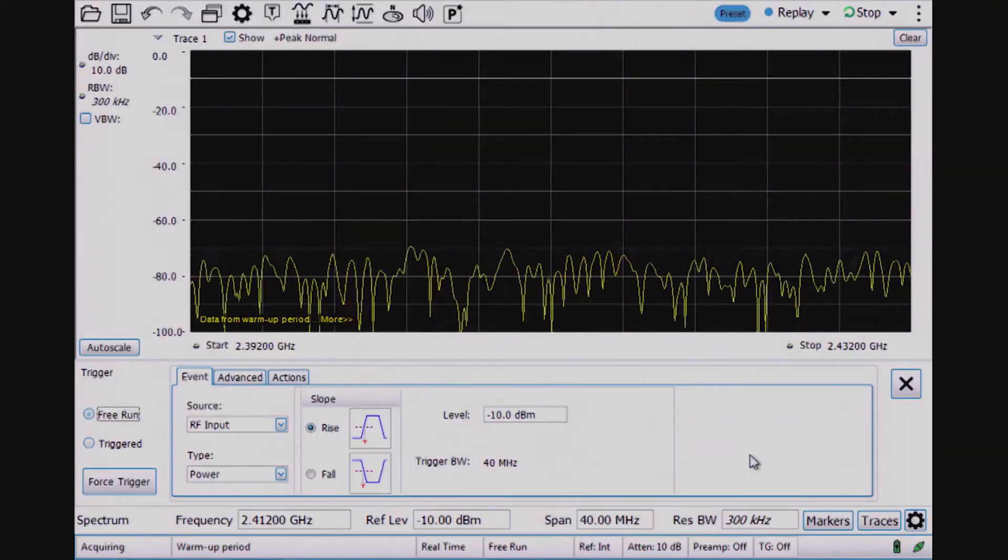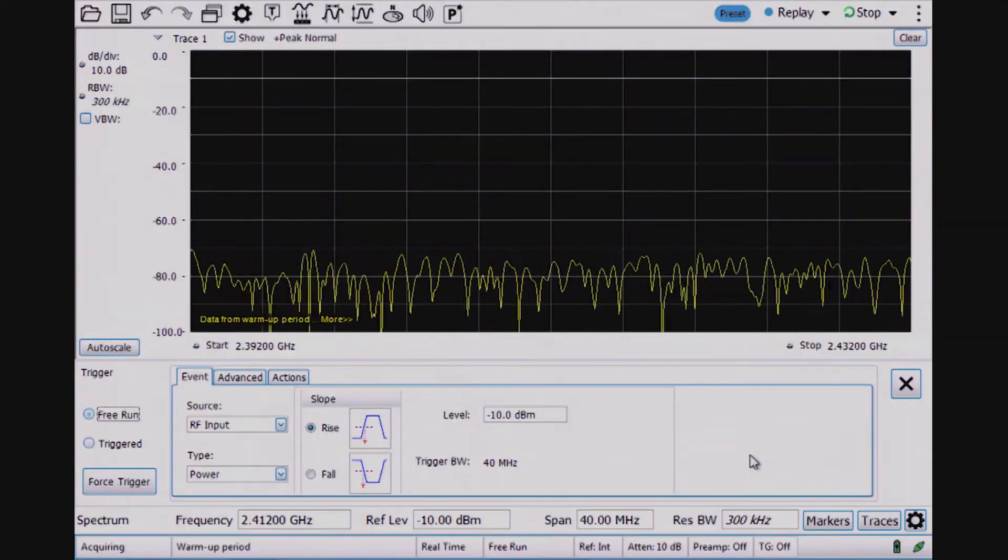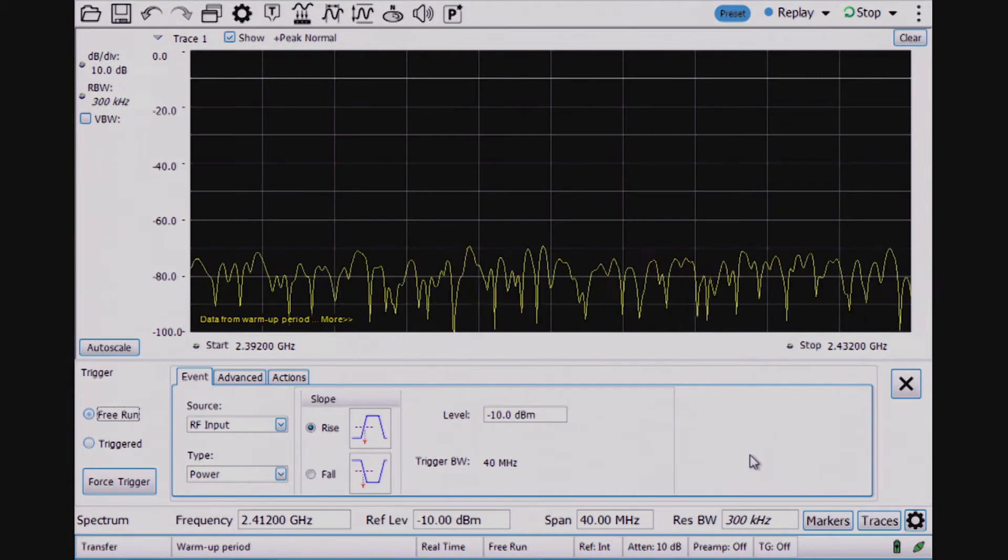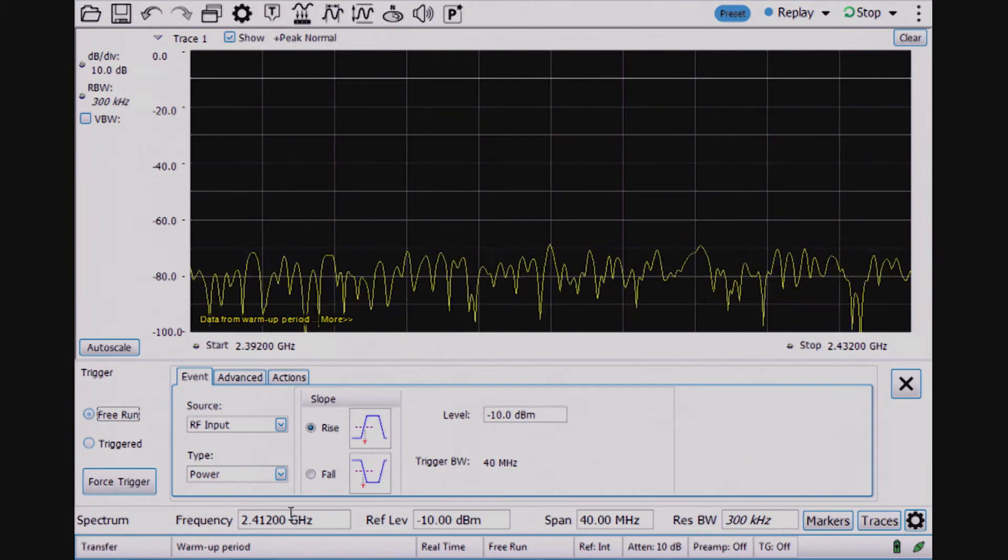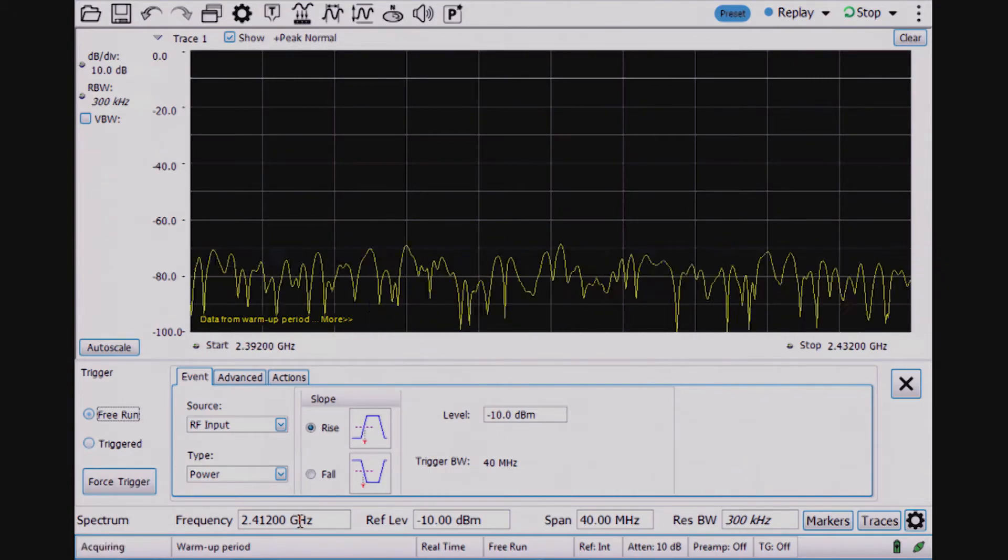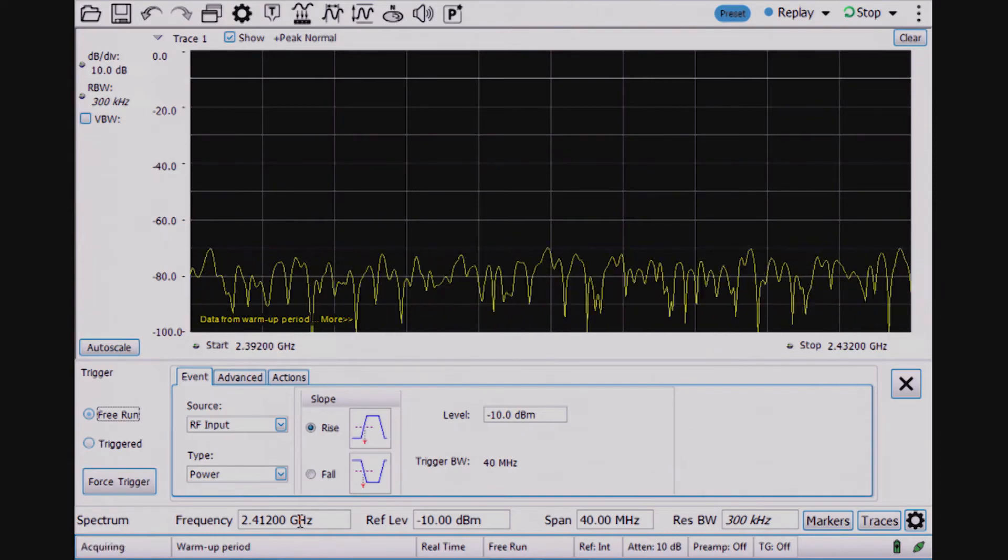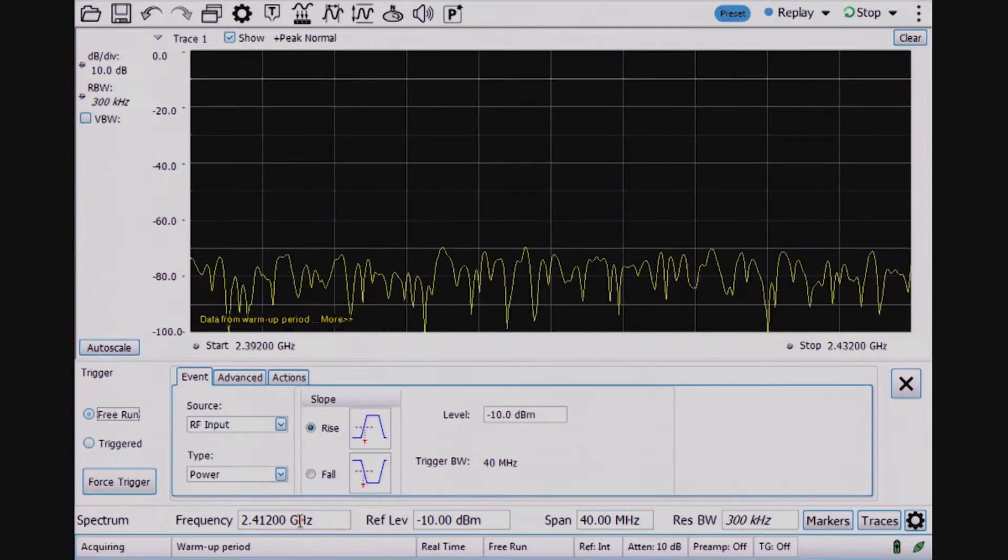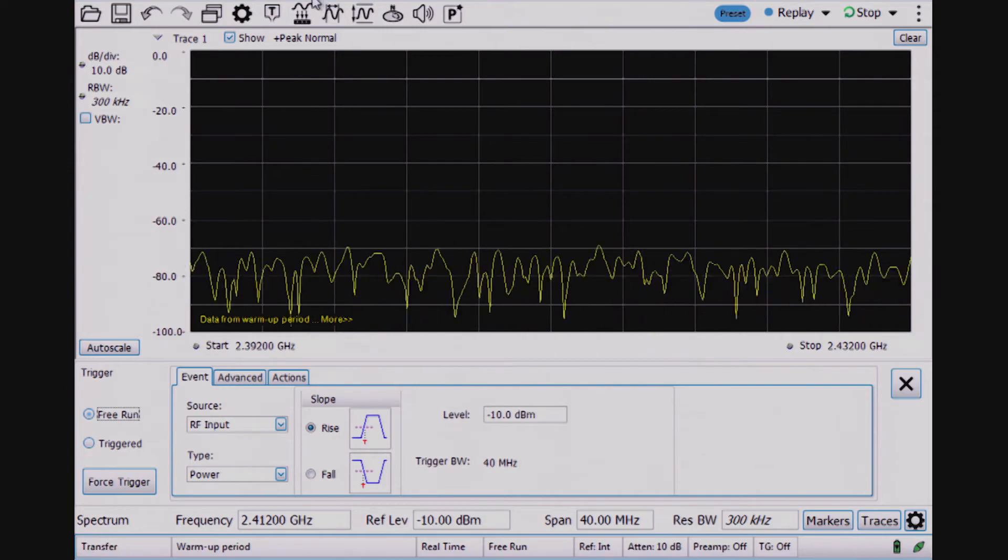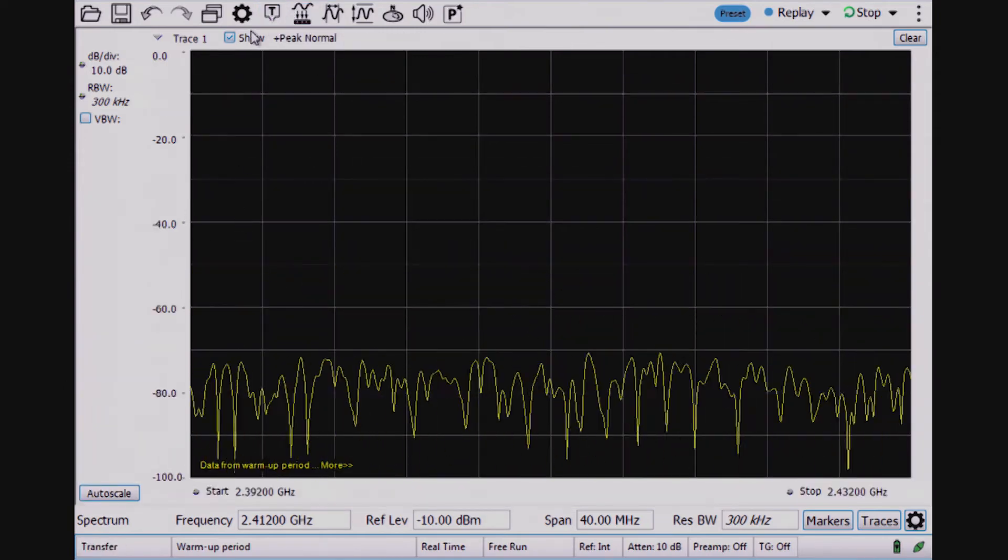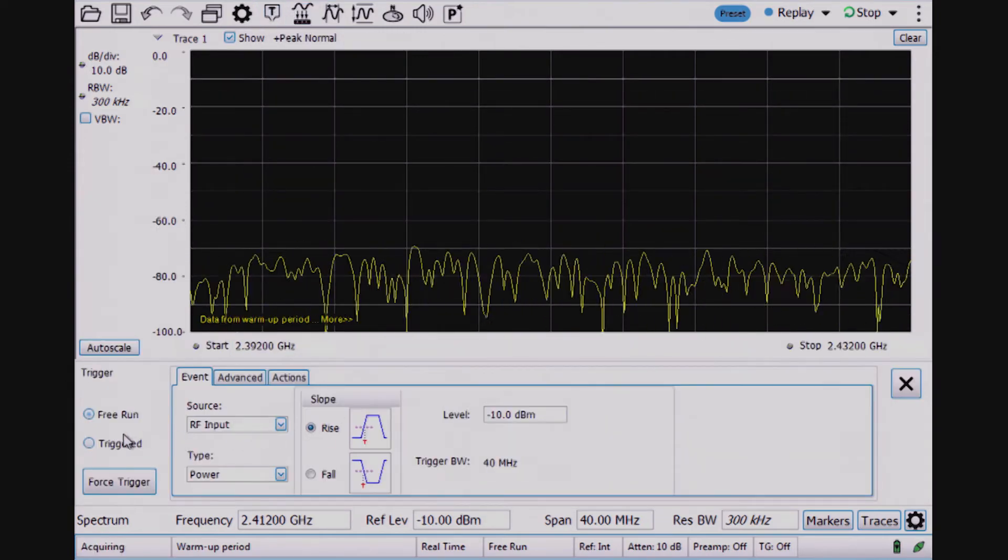What I'm showing right now is a spectrum analyzer trace at the same frequency where I have the wireless LAN module transmitting at channel one of the wireless LAN band, 2.412 gigahertz. I don't see any signal presence, so the next thing I will do is turn on a trigger.